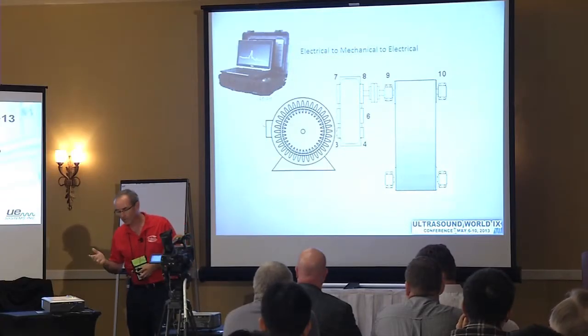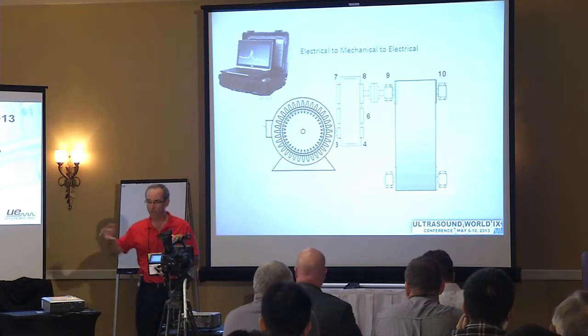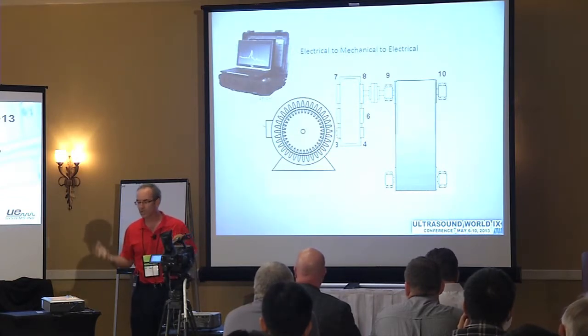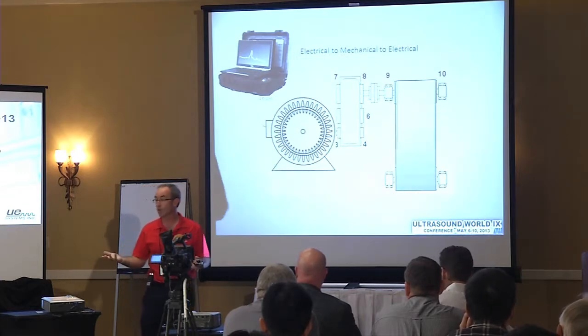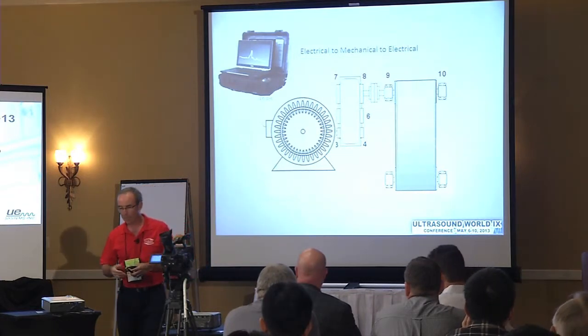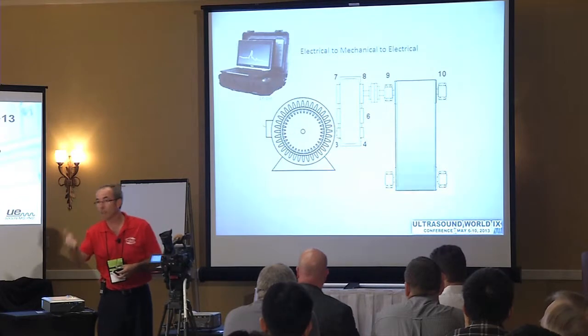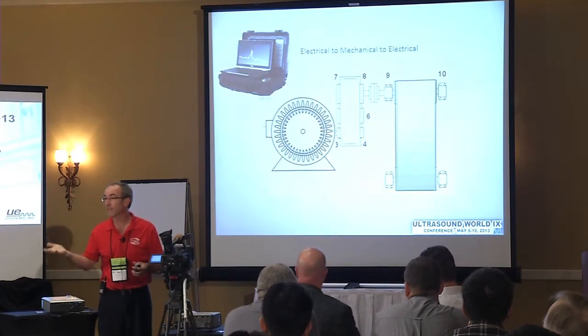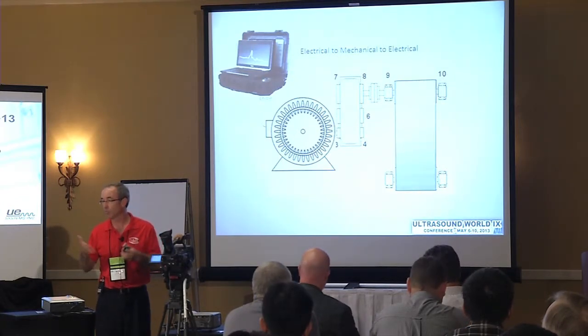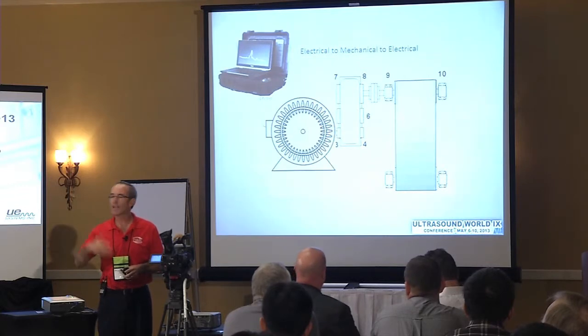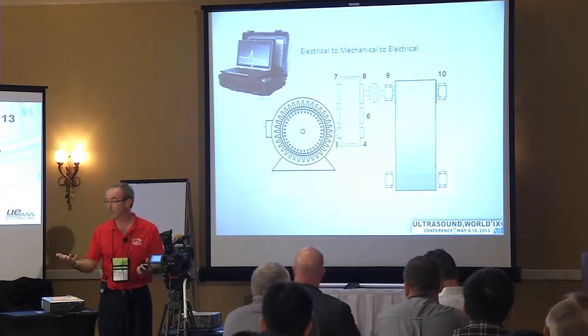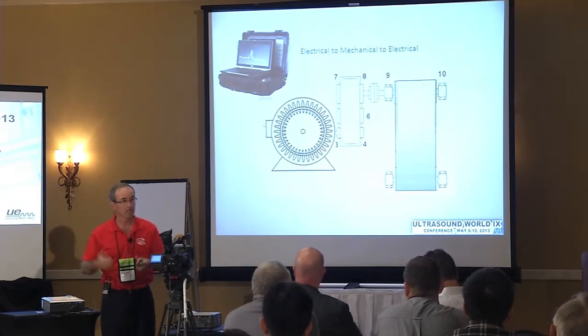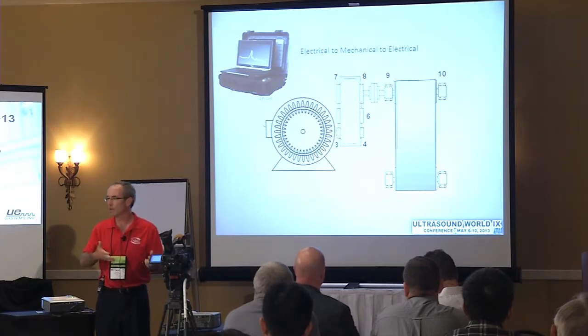We had a case study recently where the current signature data was indicating a significant increase in what we would blame on an imbalance. We can't differentiate so much between balance or alignment. We just know it was a mechanically induced, generated, broadband energy. So they contacted the vibration and mechanical analysis group, right? Which would be a lot of you guys here. And they said, hey, something's strange going on with this fan.